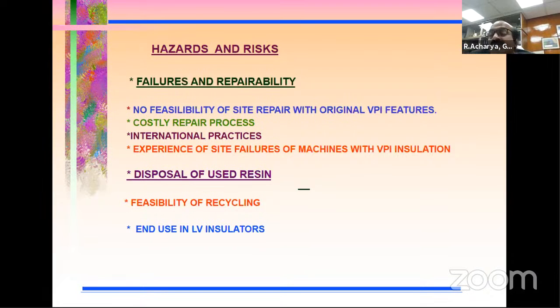The second issue is disposal of the resin. As I mentioned, the resin is reused again and again, but at any point we require almost 60 tons, or 60 kiloliters, of resin. After some time, due to rising viscosity, penetrability is lost, so the manufacturer has to dispose of almost 60 kiloliters of resin. That's a big environmental issue. But there are opportunities to use this used resin in different low voltage insulator applications and recycling. These are the environmental risks of this kind of insulation system.